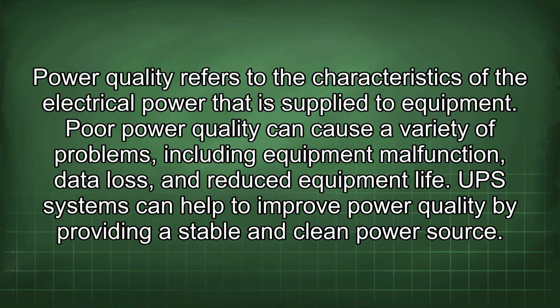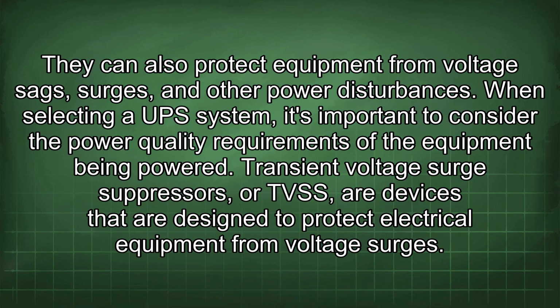Power quality refers to the characteristics of the electrical power that is supplied to equipment. Poor power quality can cause a variety of problems, including equipment malfunction, data loss, and reduced equipment life. UPS systems can help to improve power quality by providing a stable and clean power source. They can also protect equipment from voltage sags, surges, and other power disturbances. When selecting a UPS system, it's important to consider the power quality requirements of the equipment being powered.